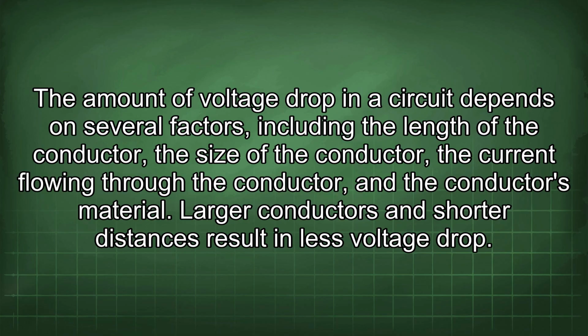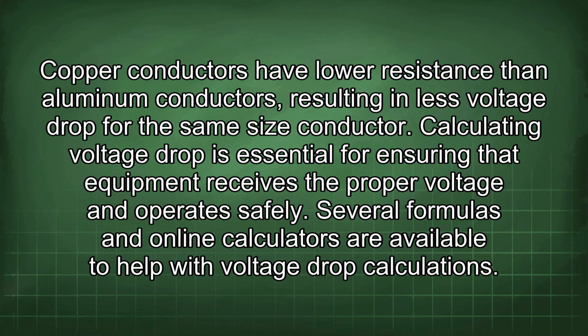The amount of voltage drop in a circuit depends on several factors, including the length of the conductor, the size of the conductor, the current flowing through the conductor, and the conductor's material. Larger conductors and shorter distances result in less voltage drop. Copper conductors have lower resistance than aluminum conductors, resulting in less voltage drop for the same size conductor. Calculating voltage drop is essential for ensuring that equipment receives the proper voltage and operates safely. Several formulas and online calculators are available to help with voltage drop calculations.